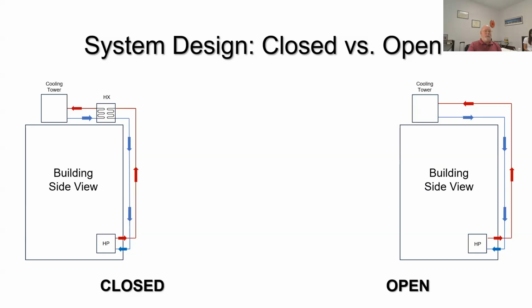As a matter of fact, certain manufacturers, AAON is one that I'm aware of, specifically bury in their literature that says, do not use this particular make and model of our rooftop unit on an open tower because it will plug up our microchannels. That's a separate presentation from this when you're doing rooftop units and things to consider.